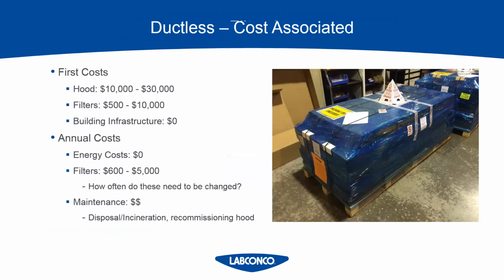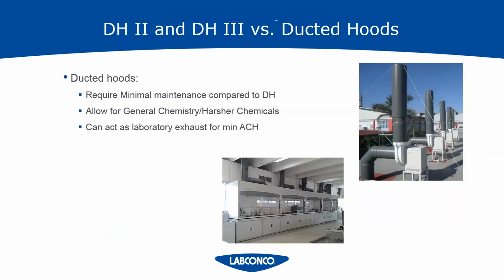And then any other costs associated would be from maintenance, which would be the labor to perform any filter changes or sensor changes on the DH3, and then recommission the hoods after all of those are done. So it's definitely not something that is minimal. You have to take into account annual costs with a ductless hood as well as a ducted hood. So your typical ducted hood has minimal maintenance after it's installed. We've established that. The infrastructure and remote blower may take some extra effort, but once they're set, you won't need to think about them for a while.